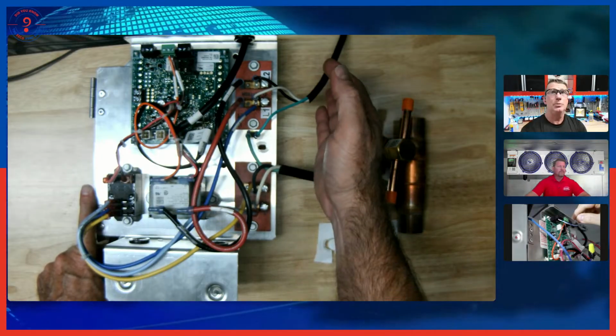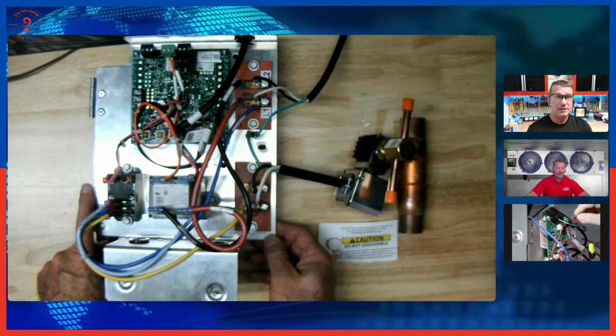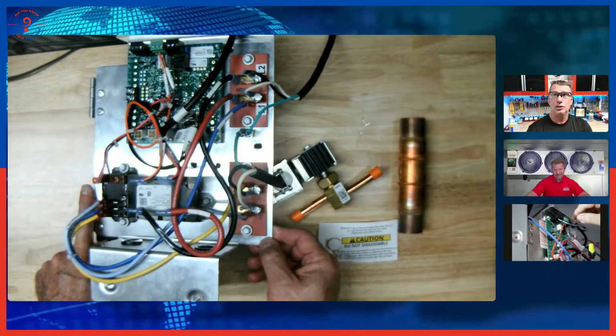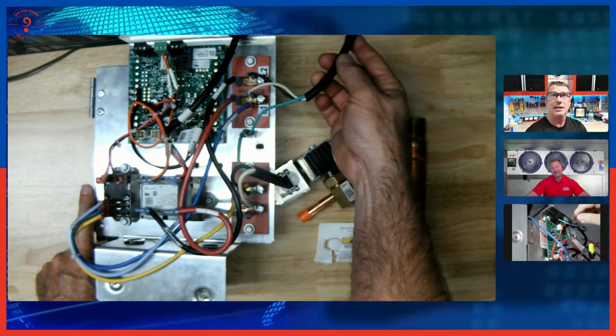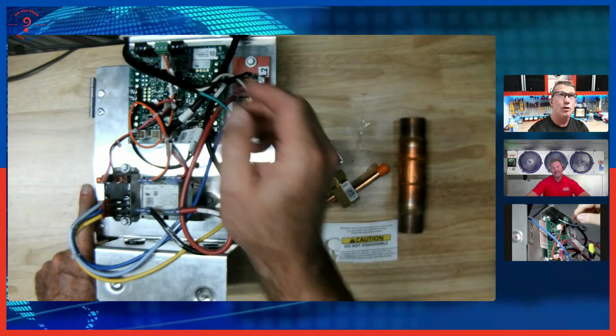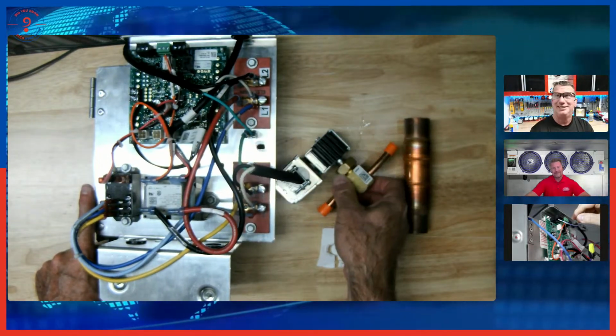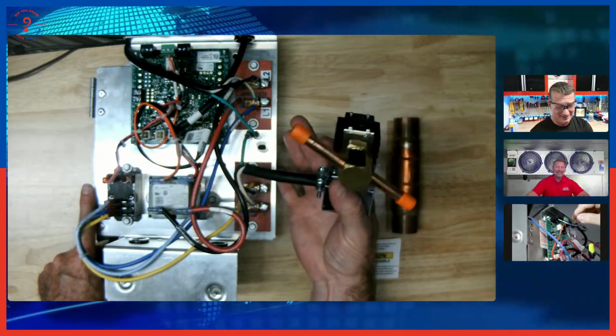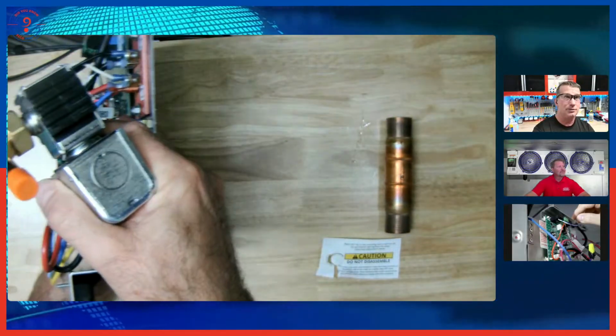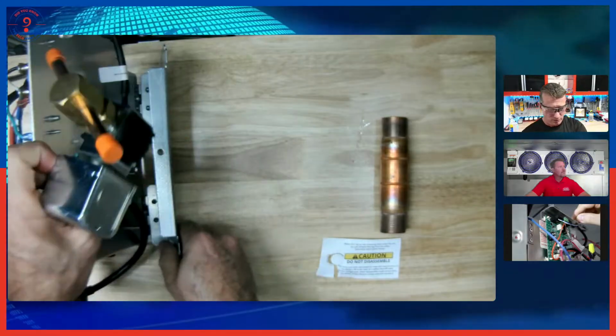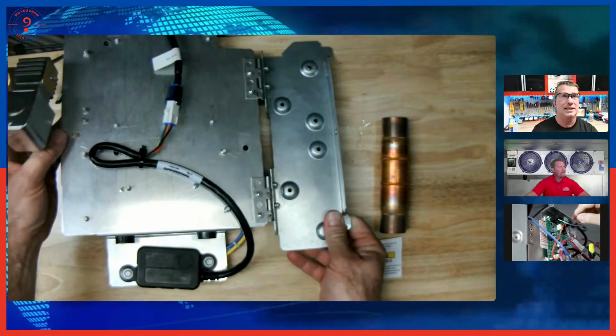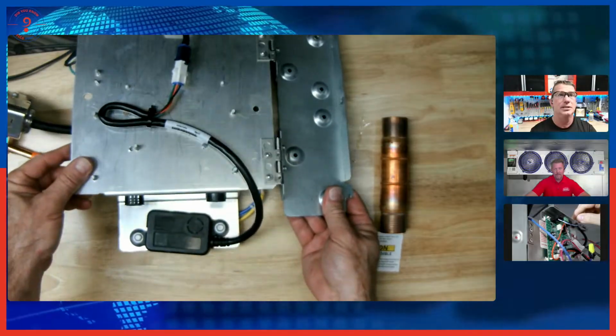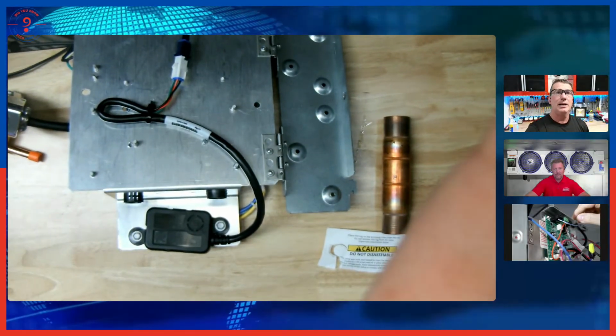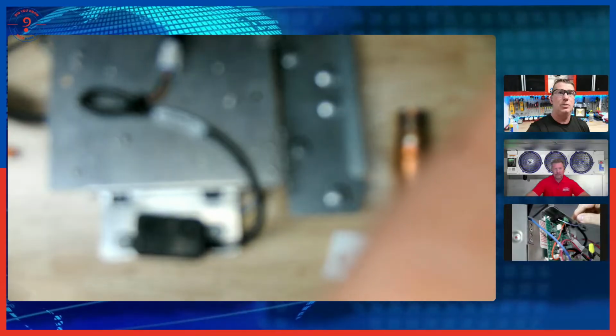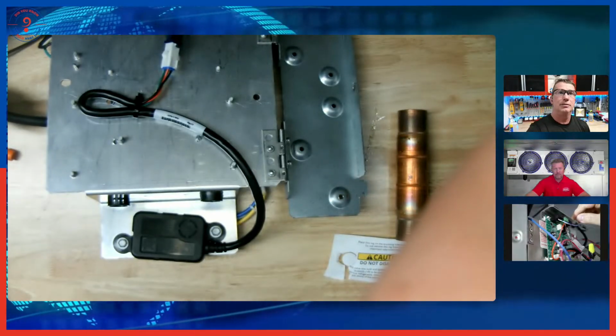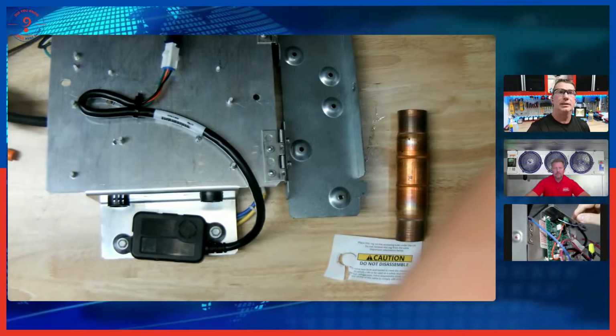Now I'm seeing exactly what you meant with the wiring, because remember, this is going to be a hinged door, right? Yes. I've disconnected power to my unit. I'm going to move the wiring over to where it should have been installed, and I have my short wiring here. And so I want to show you where this refrigerant detection sensor is. If we opened up the inside, we're actually going to see the refrigerant detection sensor here, located on the back of our electrical panel. And I'm going to see how well I can zoom into this for everyone. Yeah, that's not too awful bad, I guess.